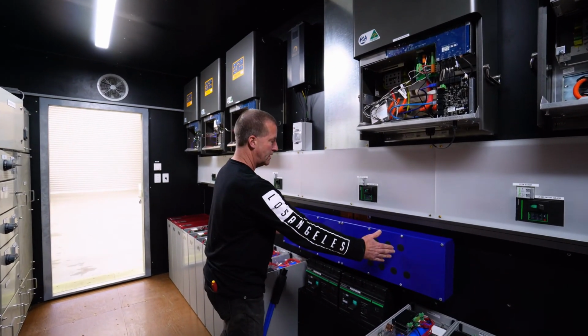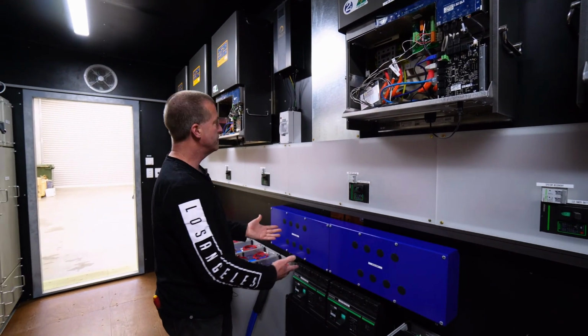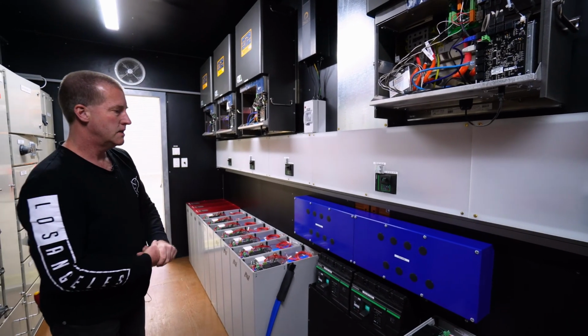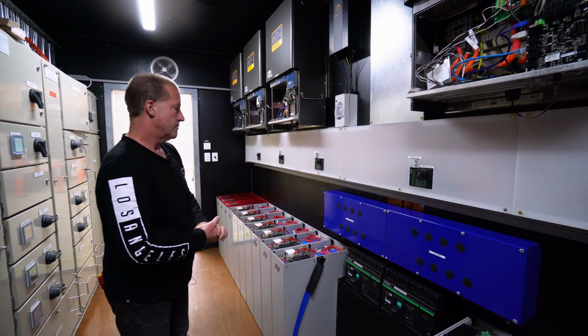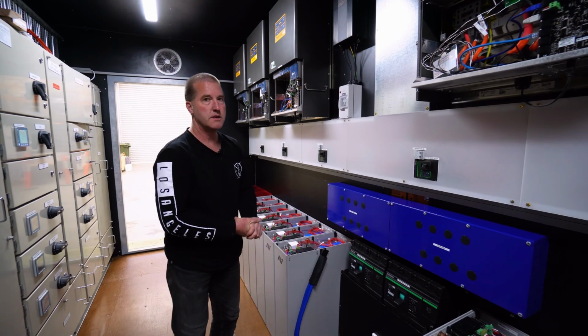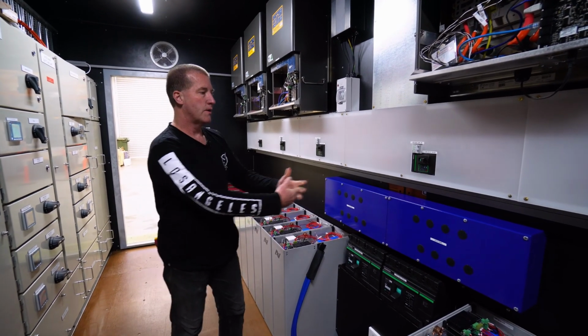We have 2 battery banks on here and then 5 inverters coming off. So why are there fuses inside the busway? Well, there's a lot of regulation around fault current and arc flash, and this is our way of dealing with that.